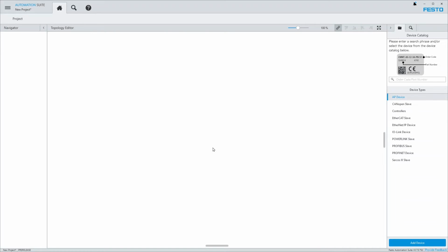In case of Profinet or EtherCAT, the parameters are set up in the development environment of the PLC by using device descriptions. With one exception: when using Festo controllers, parameters are set up in the CPX-AP plugin and then applied to the EtherCAT startup parameters automatically.